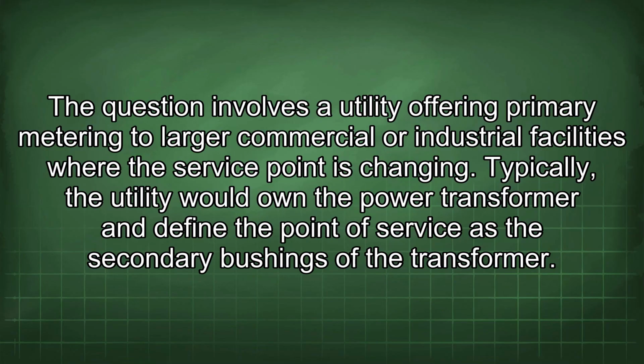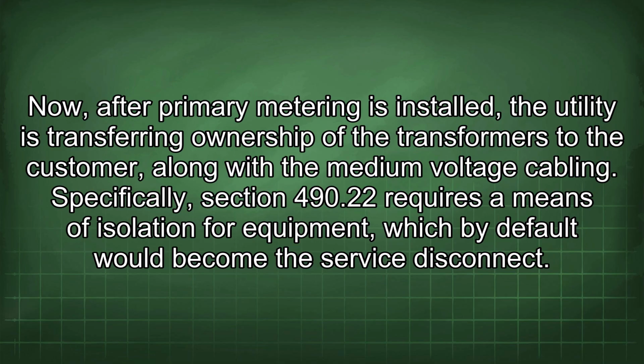The question involves a utility offering primary metering to larger commercial or industrial facilities where the service point is changing. Typically, the utility would own the power transformer and define the point of service as the secondary bushings of the transformer. Now, after primary metering is installed, the utility is transferring ownership of the transformers to the customer, along with the medium voltage cabling.